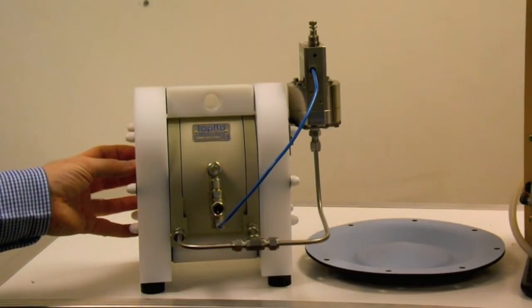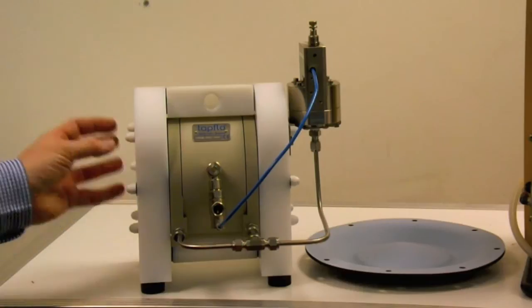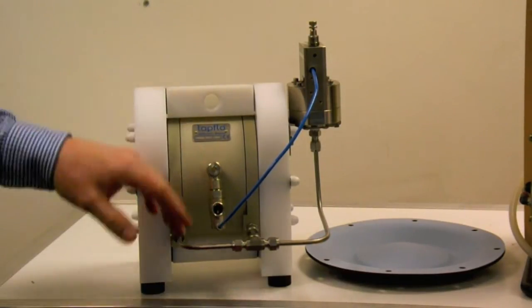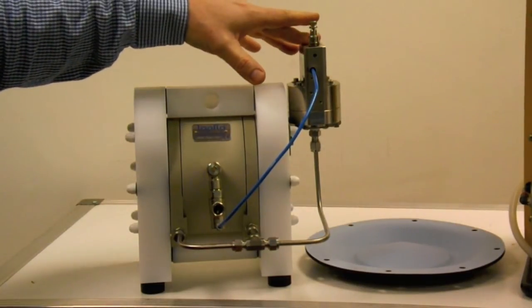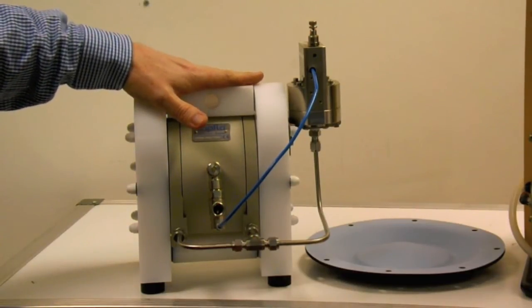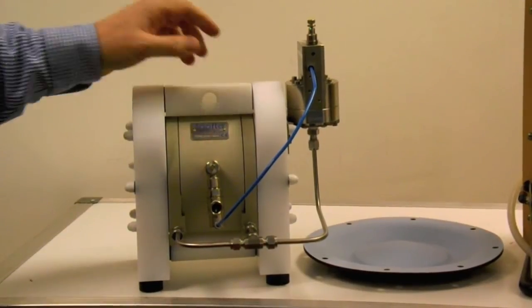If we have a failure on the primary diaphragm or the air diaphragm for that matter, the pressure would increase in that void. The pressure would thus increase going into the guardian unit. The guardian will see that and shut the pump down. So this is a very safe way of containing a spillage or containing the potential for a spillage should one occur.